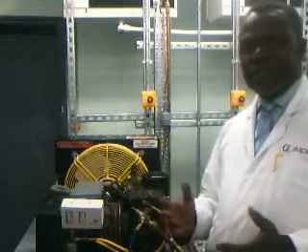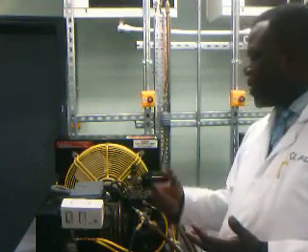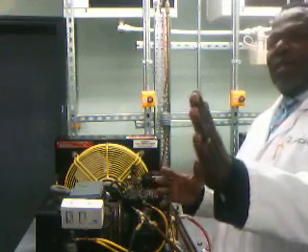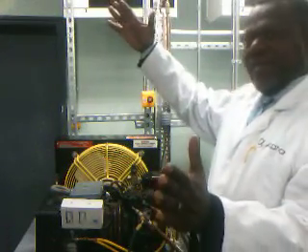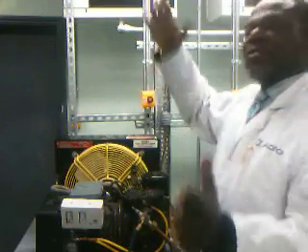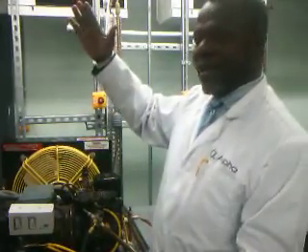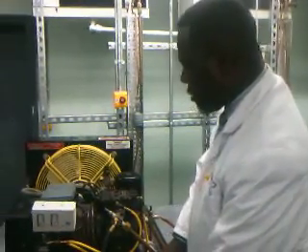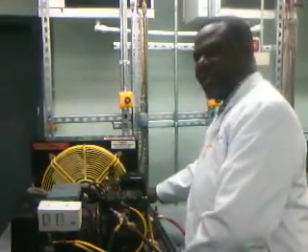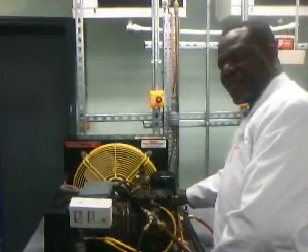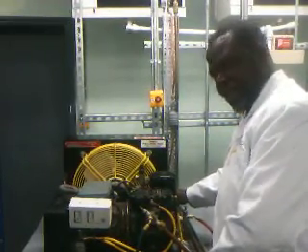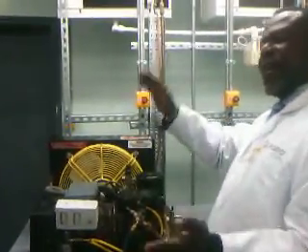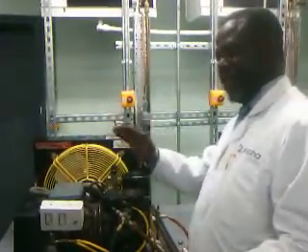Now there is a range. You have to have a subcooling of between 5 and some people say 7, but in some cases we say 5 to 10. It is the difference in temperature between the condensing temperature and the outlet temperature of the condenser. The difference should be between 5 and 7. If you get 5 to 7, that is what we call normal condensation.